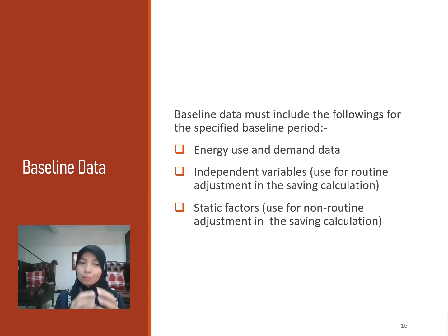Okay, where to get this baseline data? For the energy data, you can get the baseline energy data from utility meters or bills, especially when you choose option C, because for option C you need monthly electricity bills, which you can get from the utility meter. You can also have a special meter isolating a retrofit or portion of a facility from the rest of the facility. For example, for the lighting system, you install a special meter at the distribution board to measure the lighting circuit. Or for a chiller, you need a special meter to measure the energy performance of the chiller system. These refer to option A and option B.